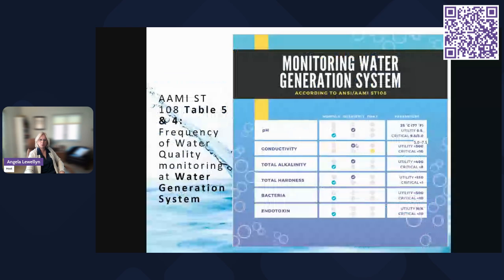Here's one of the charts: we've combined table 4 and 5, monitoring the water generation system. This is from your filtration system if you have it. You're going to test these elements: pH, conductivity, total alkalinity, hardness, bacteria, and endotoxin.